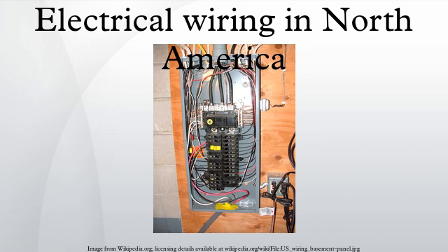Wires with XHHW insulation are commonly used in the alternating current electrical distribution systems of commercial, institutional, and industrial buildings and installations, usually at voltage levels ranging from 110 to 600 volts. This type of insulation is used for both copper and aluminum conductors which are either solid or stranded, depending on size. According to Underwriters Laboratories Standard 44, XHHW insulation is suitable for use in dry locations up to 90 degrees Celsius, or wet locations up to 75 degrees Celsius.